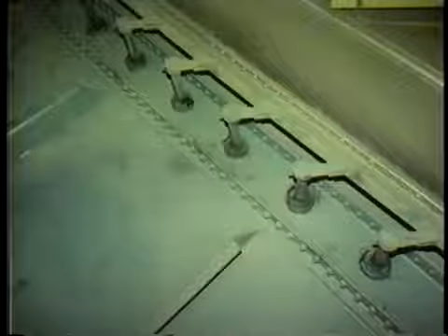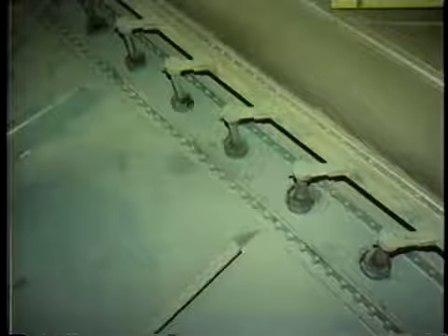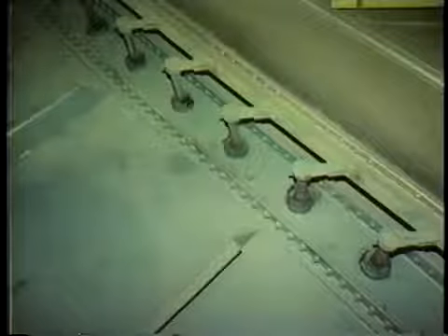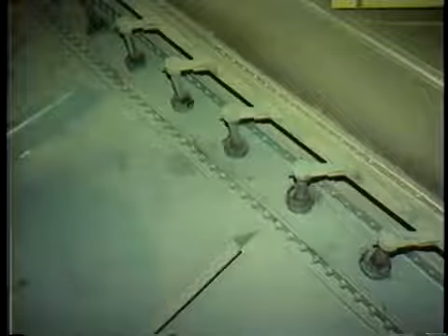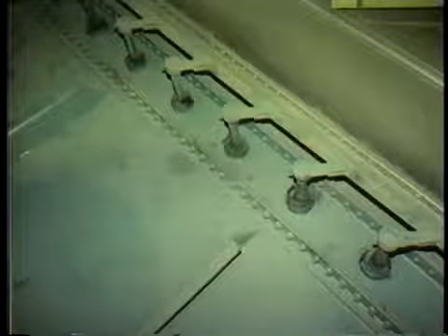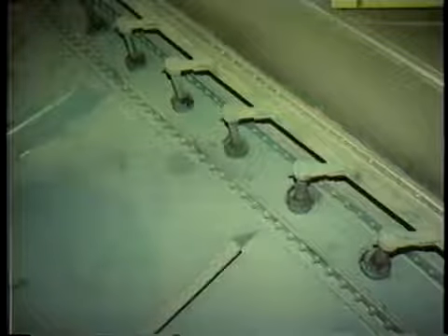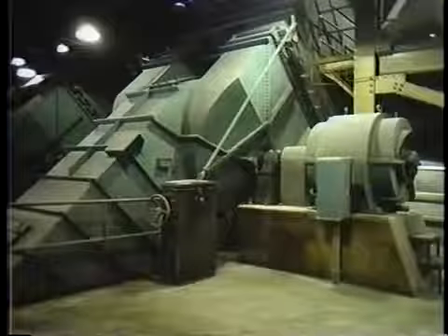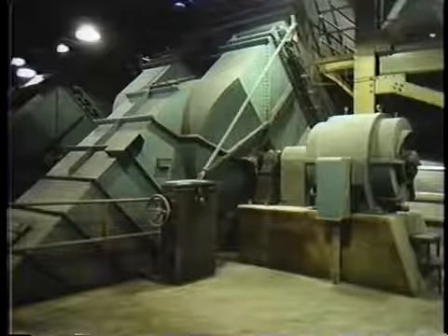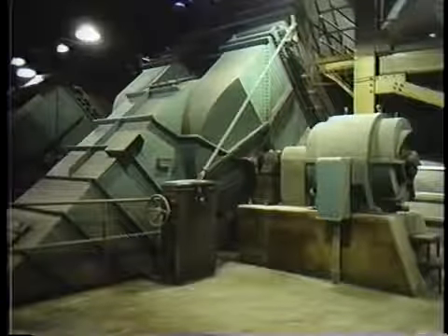If these motors fail, the fans won't work. Likewise, if the damper controller or other fan components break, the operator may lose the ability to control the flow of air through the boiler or to remove the products of combustion. Both of these situations can eventually lead to a loss of flame.